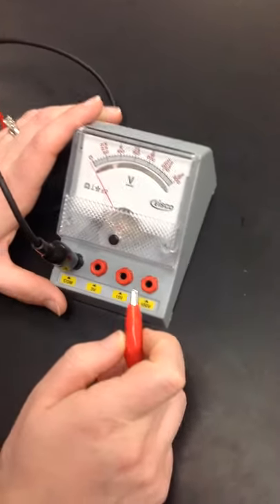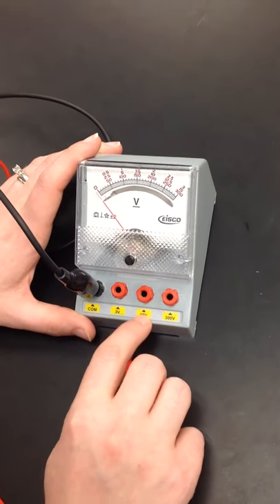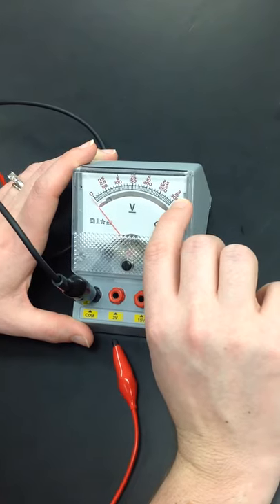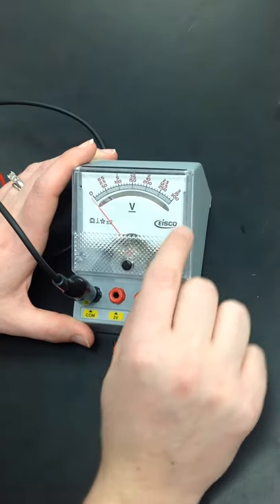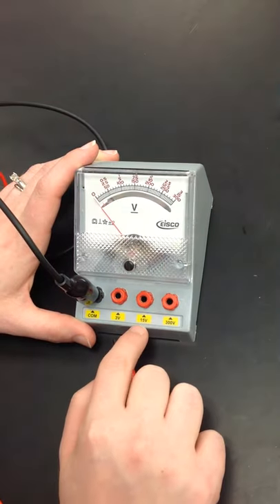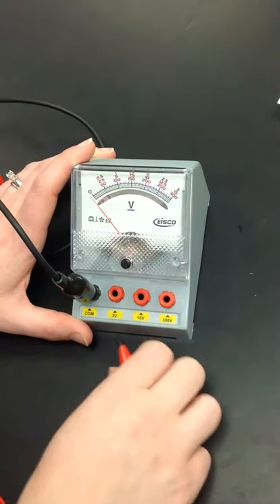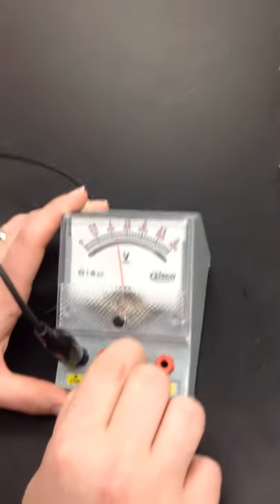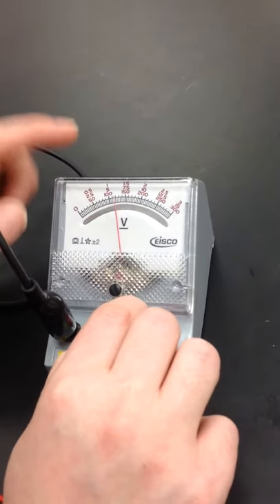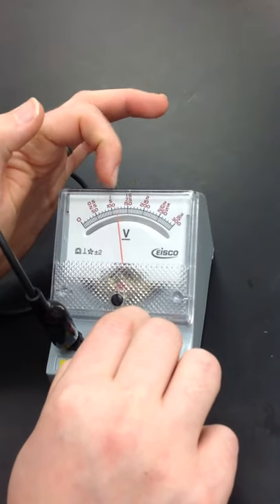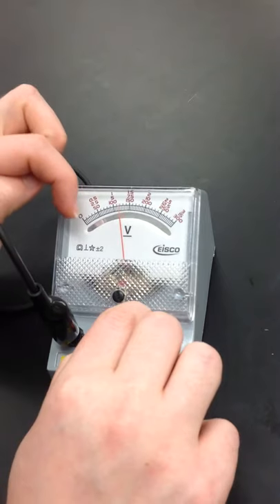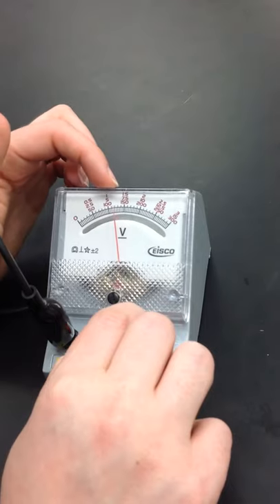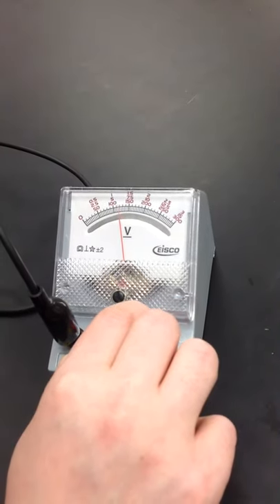So the ideal scenario is going to be for us to try 15 volts. If I plug it into the 15 volts marker here, on the scale, I'm going to look for the one that ends in 15 and that's what I'm going to read. So I'm going to choose to read the middle set of numbers because the 15 volts is the middle line here. So I'm going to plug this in here. And when I do, I can see that I have reading the middle set of numbers. It's a little bit past the five and before the 7.5. And I can even use these little small hashes to help me out. And I can see that I've got just under six volts of charge coming from the battery.